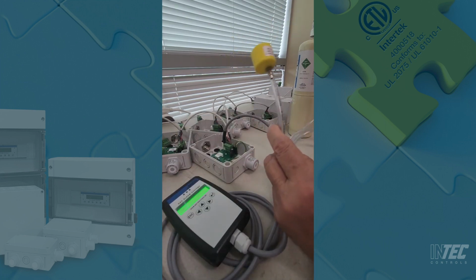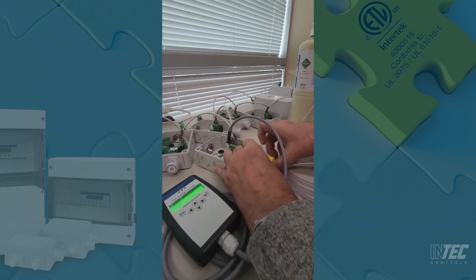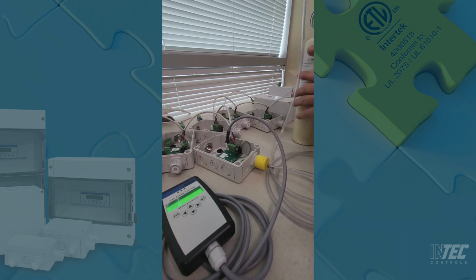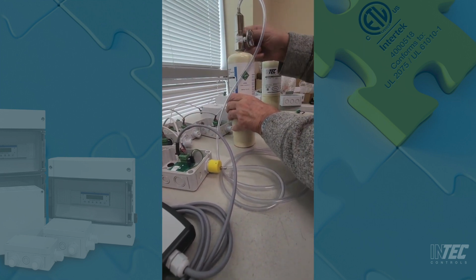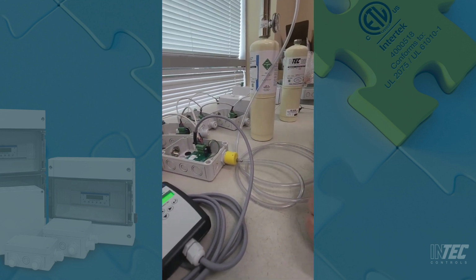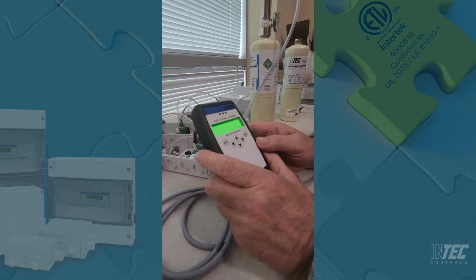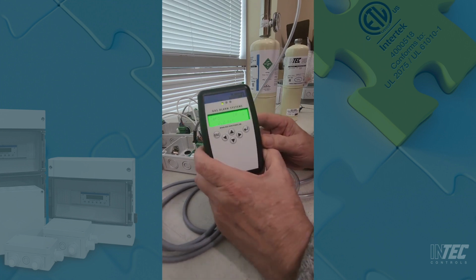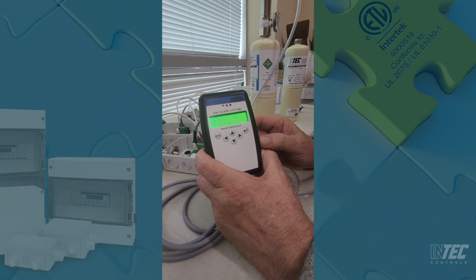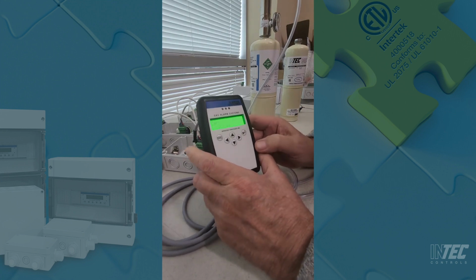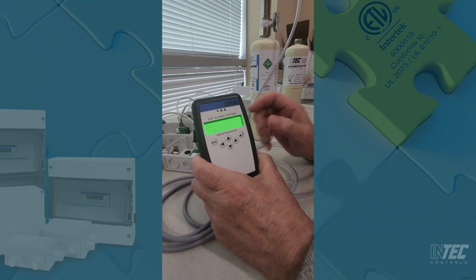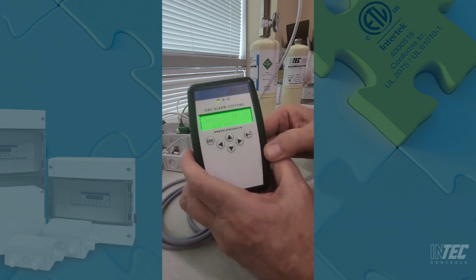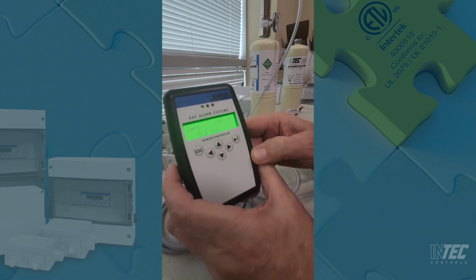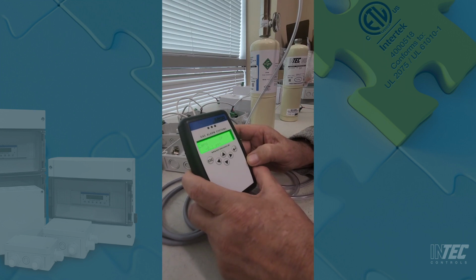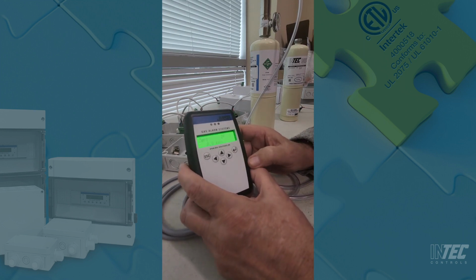This is when you're going to apply your yellow cup to the sensor head. And then you're going to turn on your zero gas nitrogen to the sensor, and let that run for about a minute. We can see now on the screen that it's reading 0 ppm, so we're going to go ahead and hit the enter button. You'll see the cursor moving across the bottom of the screen. You're going to let this run to stabilize out for a few minutes, and when it's reading 0, just hit enter. It'll say save, and it showed 0 ppm.